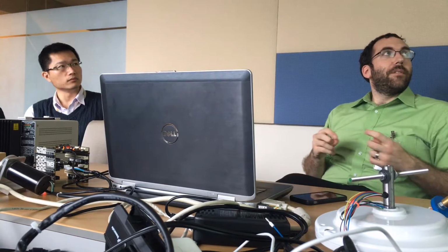It also will do some adaptation. It'll adapt the identification based on faults. So if we have overcurrent faults, it'll adjust the current thresholds, for example. It'll adjust some speed thresholds. It'll do some automatic adjustment during the identification process. It'll also adapt the drive based on the results.